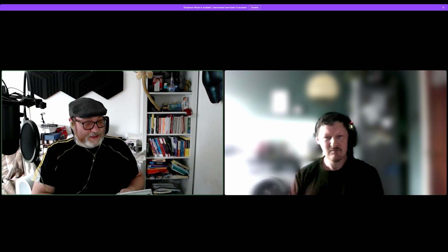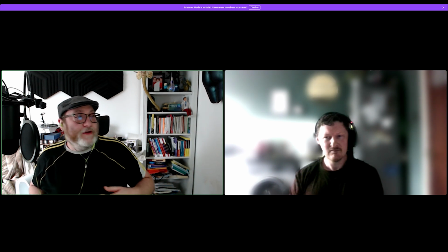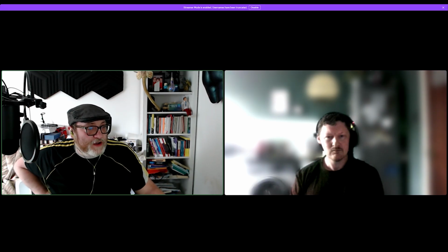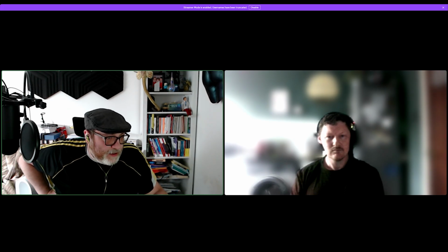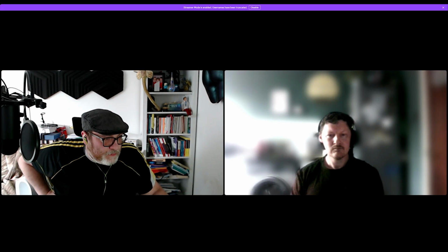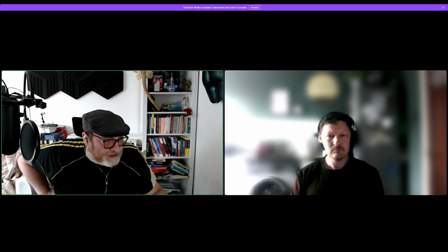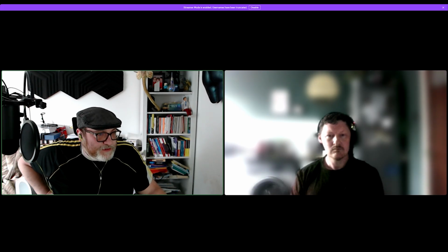Okay, fantastic. Well, that's a bit more technical CPD than I've been doing. I was just reading more about those RCDs to verify what I said last week. I've been looking up the Type B and the B plus. So I was right last week where we said that the B plus is referencing a VDE standard. And there was an article on the Hager PE website that said the devices are specified to be engineered to function at frequencies greater than 20 kilohertz, ensuring a minimum threshold of 150 milliamp at frequencies above 1 kilohertz.